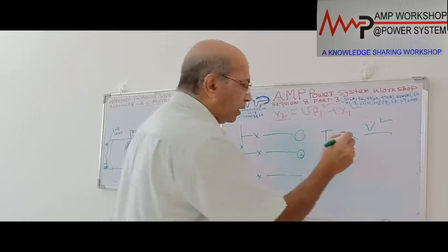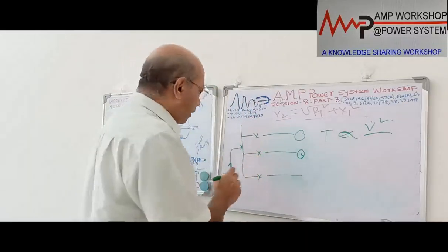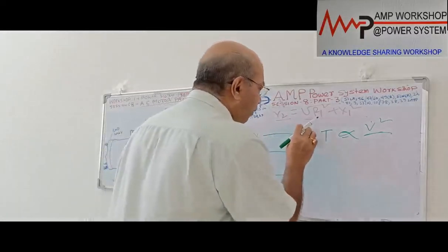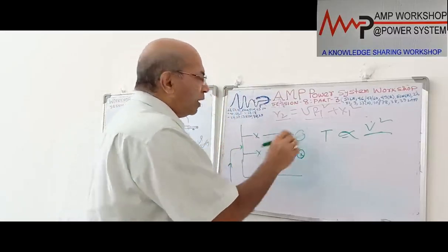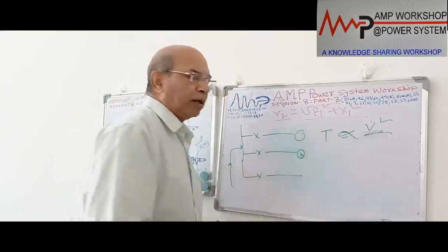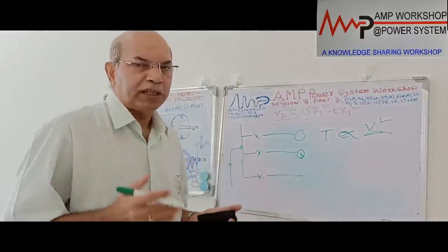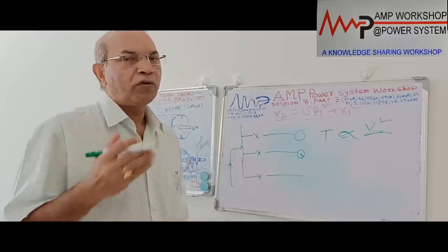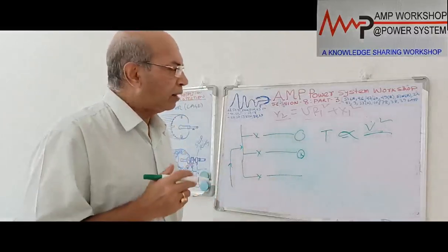Second thing, this is another way it can happen. The power system is connected, but it is under voltage and cannot cater for the motor. So the motor may be in a stall condition and is trying to draw power, but enough power is not there due to the low voltage. Or if the voltage is at a certain low value, it can run but not at the required speed. In that case, it will draw huge current, so due to high current, the motor winding temperature will go up. So in both cases, we need to protect the motor.